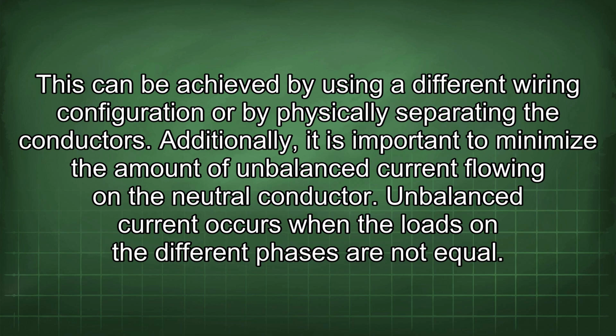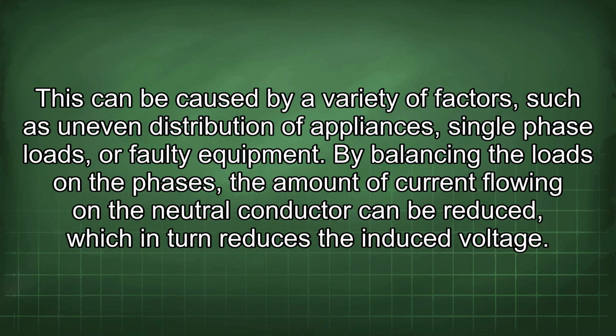Additionally, it is important to minimize the amount of unbalanced current flowing on the neutral conductor. Unbalanced current occurs when the loads on the different phases are not equal. This can be caused by a variety of factors, such as uneven distribution of appliances, single-phase loads, or faulty equipment. By balancing the loads on the phases, the amount of current flowing on the neutral conductor can be reduced, which in turn reduces the induced voltage.